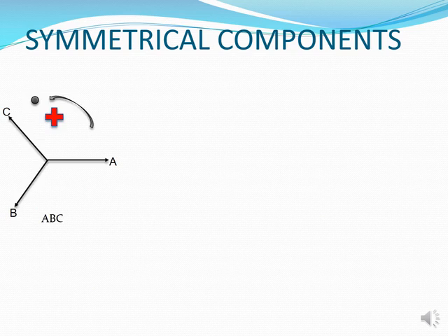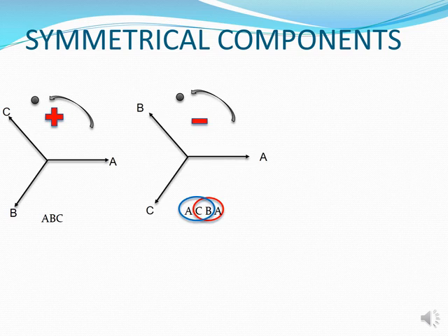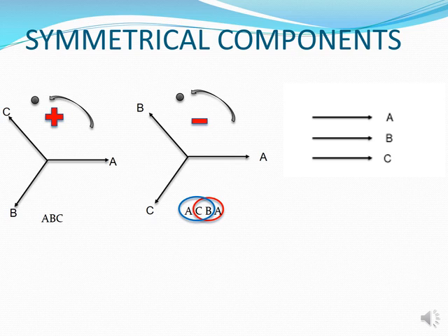The first sequence I'm introducing is the positive phase sequence, followed by the negative phase sequence, and then the zero phase sequence. For the positive phase sequence, I've written ABC at the bottom of the phasor with a plus sign. If your axis rotates and goes through the dot at the top, it must follow a sequence of ABC. So A sits at zero degrees, B at minus 120 or 240 degrees, and C at positive 120 degrees.